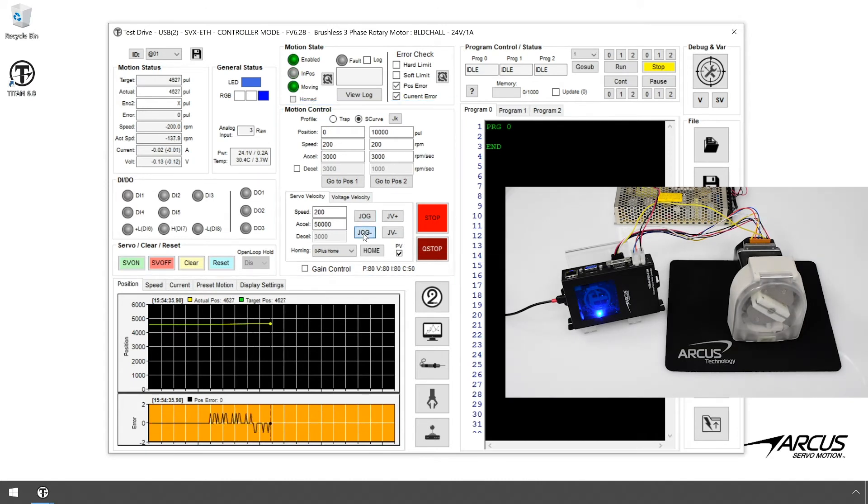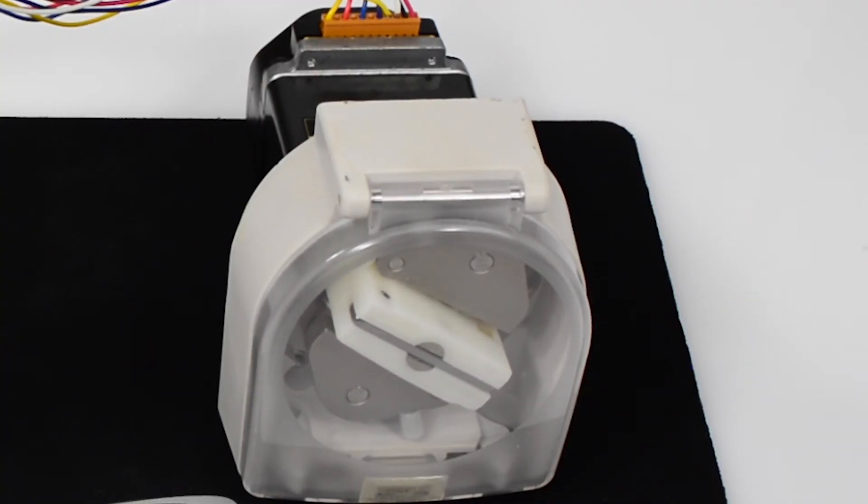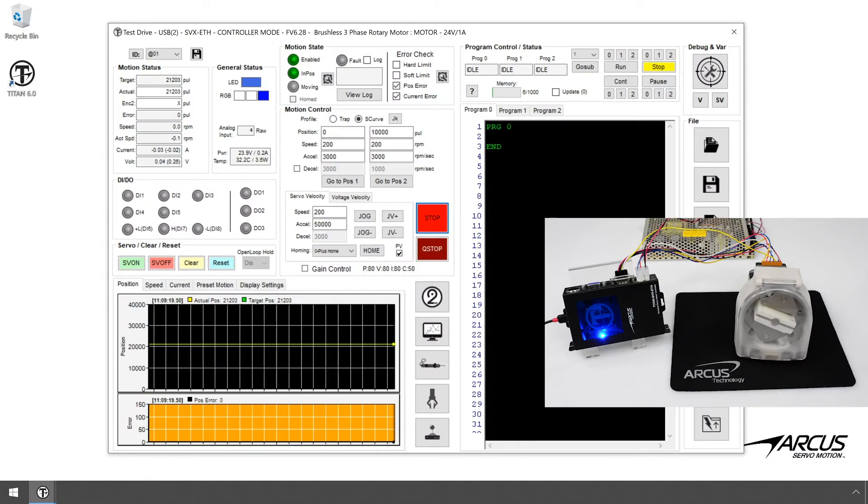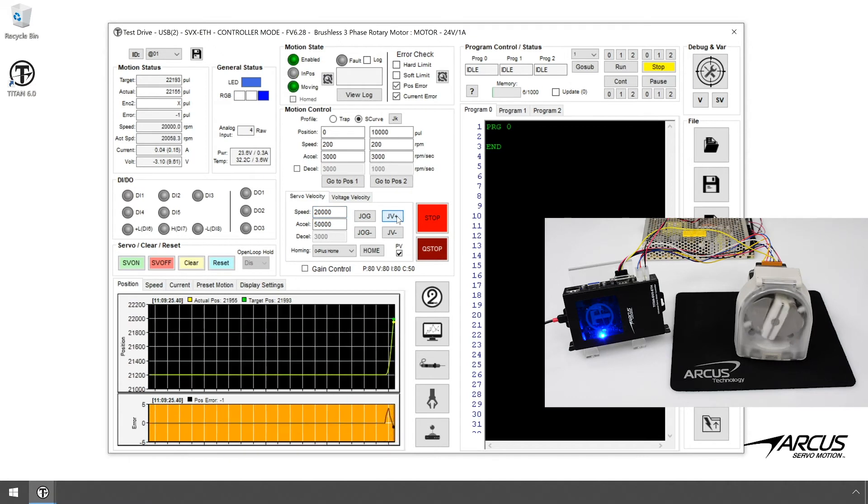You will notice that when you move the motor at slow speed, the motion will be jerky, since the Hall sensor resolution is low. So typical applications for such motors should be high-speed velocity control applications, such as a conveyor or spindle control.